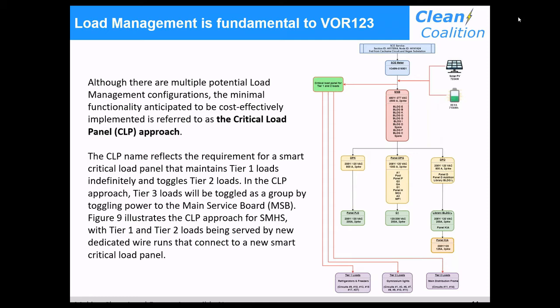The tier 2s through the critical load panel can be prioritized and force-ranked, such that the least important of the tier 2s would be the first to turn off, and so on. So the critical load panel approach is relatively cost effective and relatively precise in making sure you're serving your tier 1s forever, toggling your tier 2s in an automated fashion, and toggling your tier 3s as a block - also automated, but either all on or all off. There are other approaches to load management, but the critical load panel approach is a nice compromise between precision and cost effectiveness.